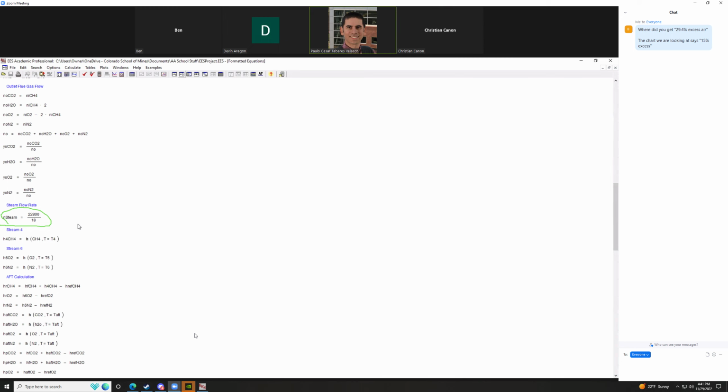So work on that, and then that will be the only thing. My only concern is that the gas flow data sounds a little sketchy. I don't know, because the data I have here is slightly different. Actually, it's very different on that one. That's the only thing I could think of. If your gas flow rate is way too high, that could make things come out very low, right? Because your boiler efficiency should be way higher, which made me think that somehow your flue gas flow rate is way too high.